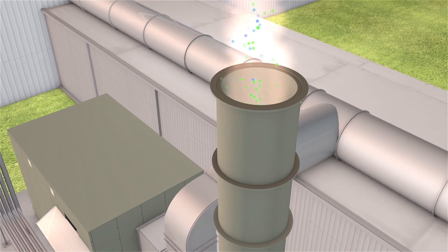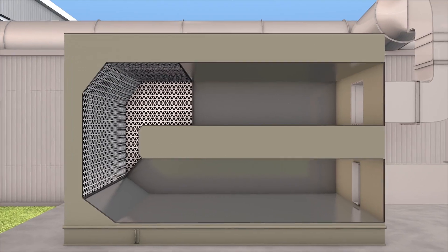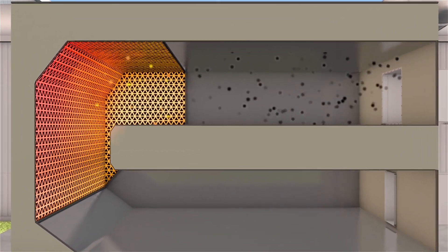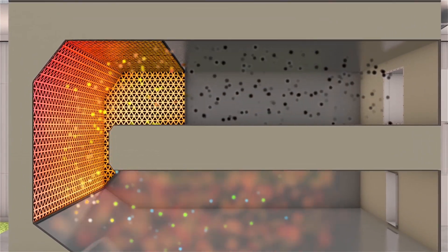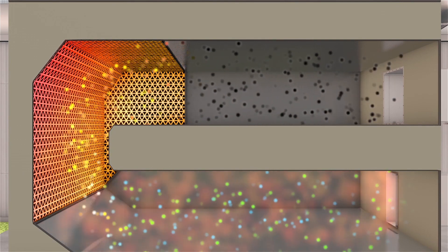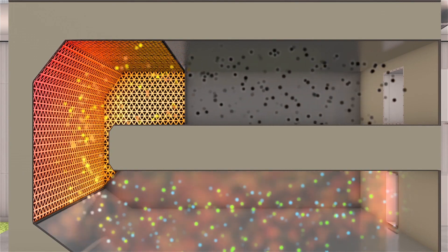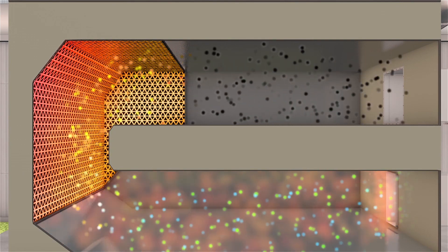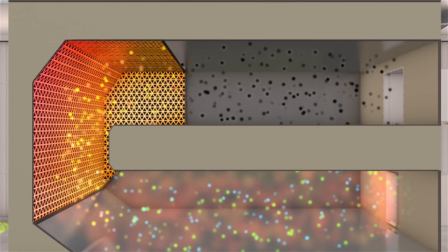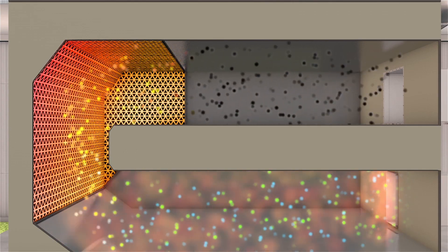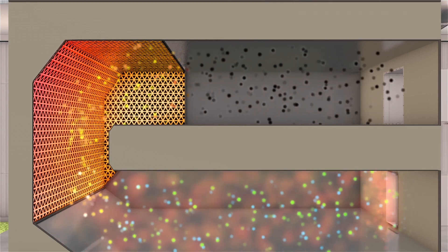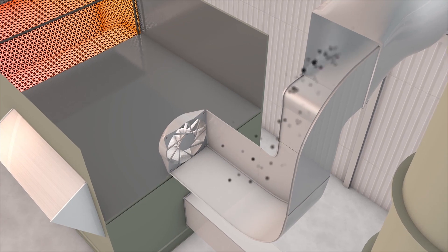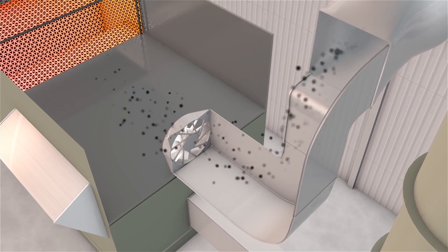It all starts with the chamber, which houses the heating element to burn the VOCs. The chamber is heated to a set point temperature of approximately 1500 degrees Fahrenheit. Once the set point temperature is reached, the fumes are brought into the chamber through a system fan.